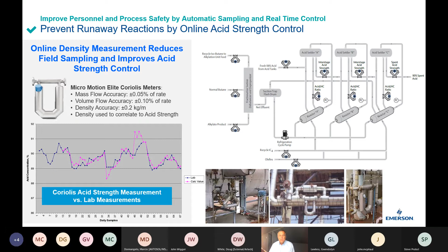There's one more, and this is around smart meter verification. Traditional methods of verifying meters include taking the meter out of service and then calibrating it offline in a laboratory. So we've designed electronics and diagnostics so this can be automated. You can go through the whole calibration procedure and check the health of the instrument and accuracy online and have measurement confidence in the end as a result. So this is a way of automating that procedure as well. Okay, so these are all good. These were three examples. And then these are the references.